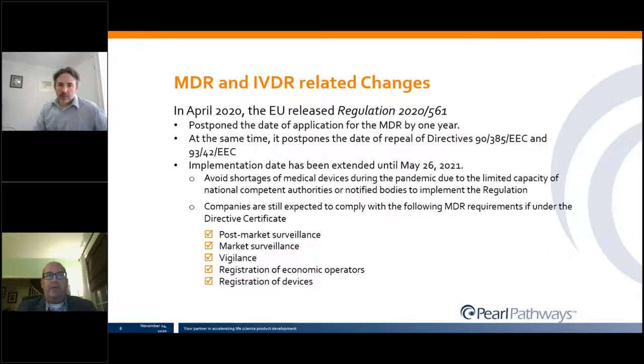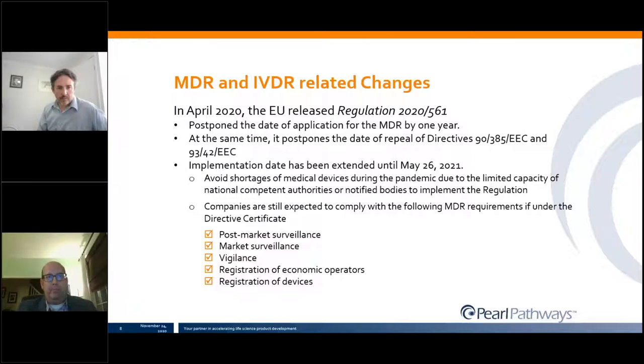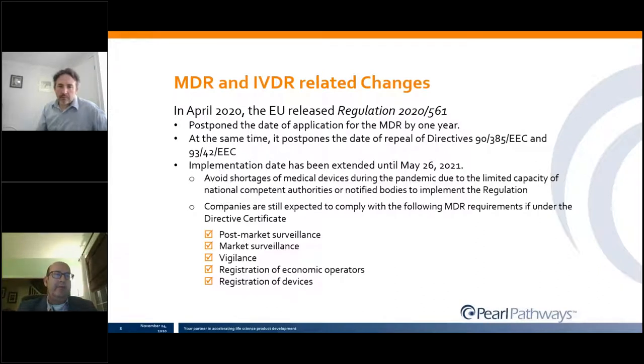In April 2020, the EU released Regulation 2020-561, which delayed the proposed date of application for the Medical Device Regulations by one year. It also postpones the date of repeal for the existing directives — both the MDD and the active implantable medical devices directive. Implementation dates were extended until May 26, 2021, in an effort to deal with limitations and shortages related to the pandemic.